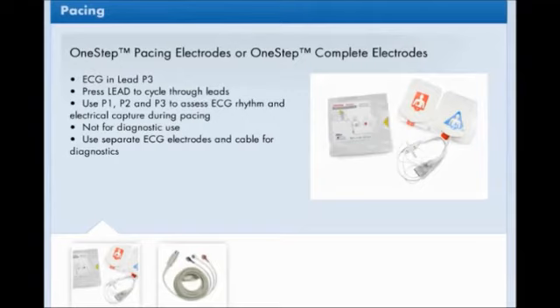It is important to note that while ECG signals acquired from P1, P2, or P3 are appropriate for ECG rhythm assessment and to determine electrical capture during pacing, they should not be used for diagnostic purposes. Use conventional ECG electrodes and a separate ECG cable for that purpose.